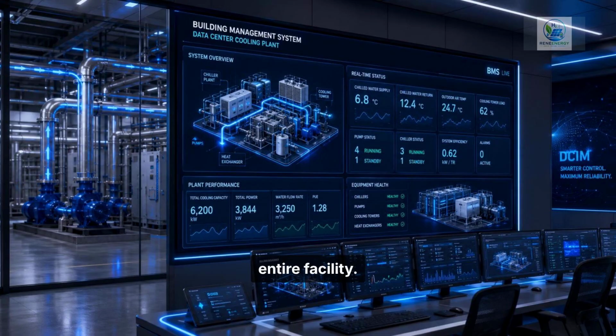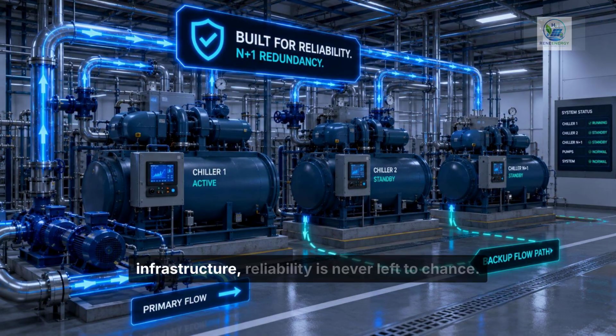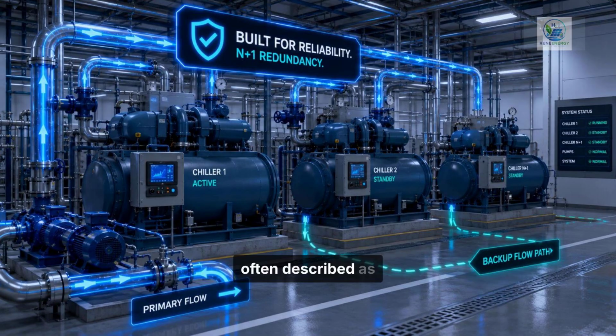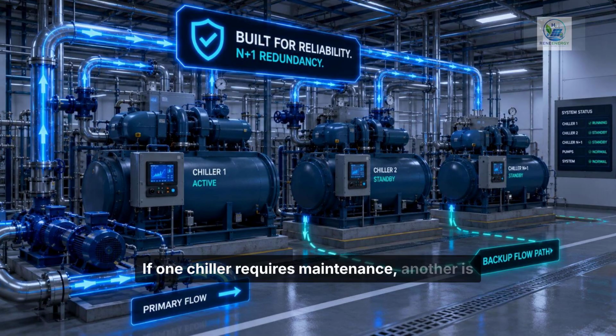In AI infrastructure, reliability is never left to chance. Every critical component has a backup. This engineering philosophy is known as redundancy, often described as N+1 design. If one chiller requires maintenance, another is already available. If a pump fails unexpectedly, an identical backup immediately takes over.